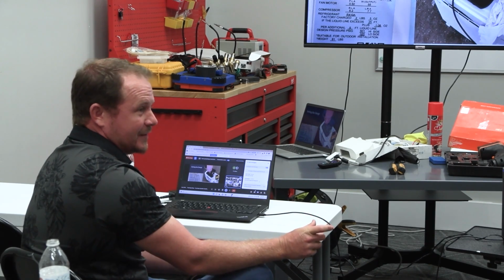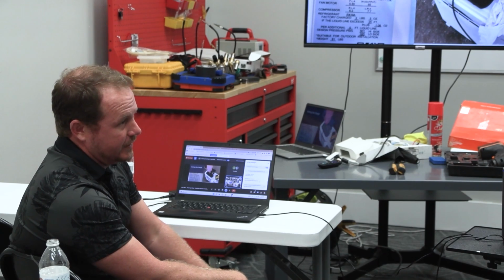Just similar to what we talked about just today on doing a decay test directly on your micron gauge. If you've ever tried to valve off a micron gauge with a ball valve and see what it does, the thing jumps sky high in a matter of seconds. And it's not because there's anything wrong with the micron gauge. It's because there's such a tiny amount of internal volume that you're pulling a vacuum on in that case. So what we're saying is, you take a little tiny hose with a little ball valve and your micron gauge, you hook it up to the pump, you pull it down real deep, you valve it off, and you see how quick your micron gauge rises. Just do it sometime. The thing will just go bananas on you. And it's because there's such a tiny internal volume and everything leaks. Every ball valve leaks, every seal leaks, your micron gauge itself leaks, everything leaks. So the more volume that you have behind it, the slower that rise is going to be.